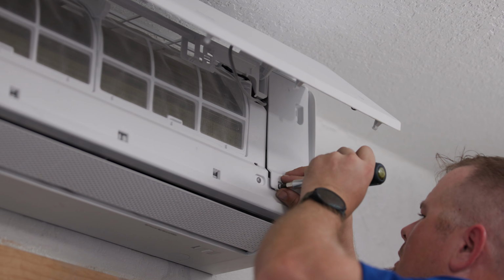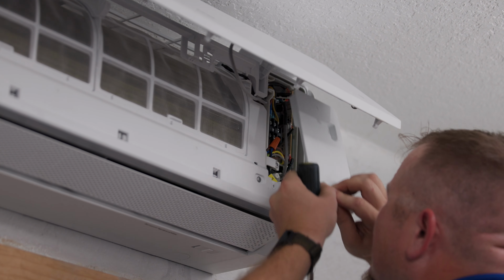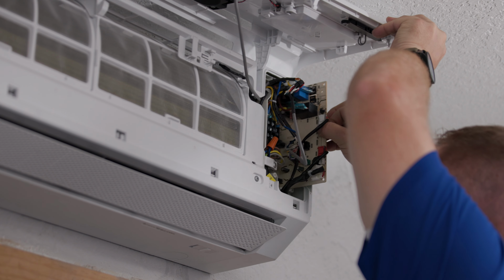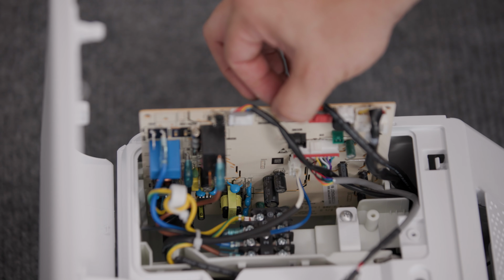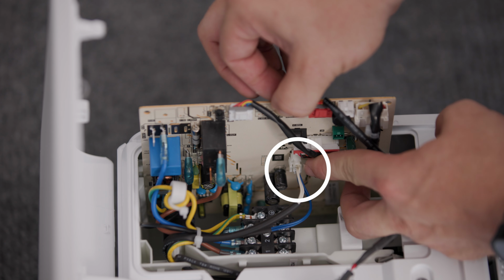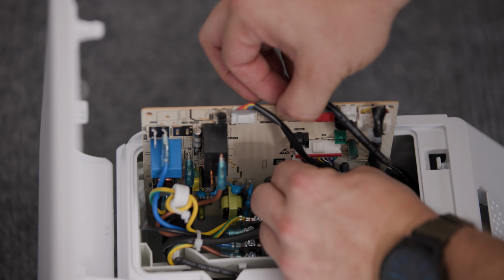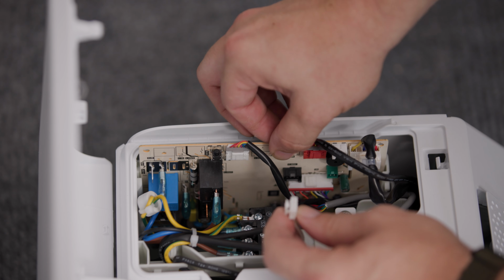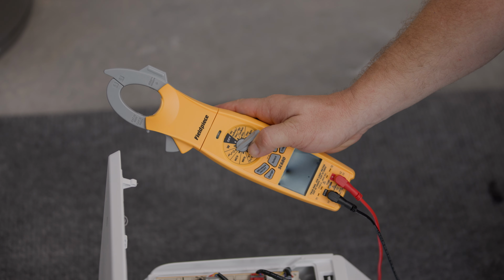Once you've identified the thermistors, use a screwdriver to gently remove the panel and slide out the vertically placed PCB. Look for a small sensor harness with 4 wires. That's your indoor unit thermistors. Unplug the thermistor from the connector carefully. To test the thermistor, set your multimeter to resistance mode. Look for the omega symbol. Place the probes on the thermistor's 2 terminals.